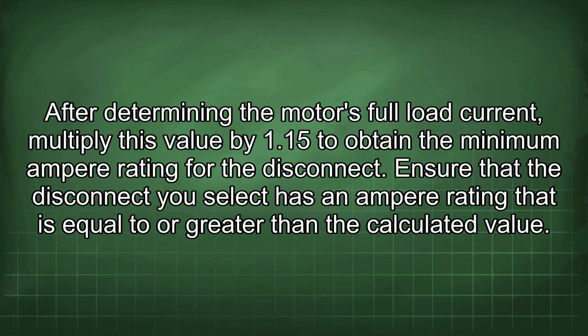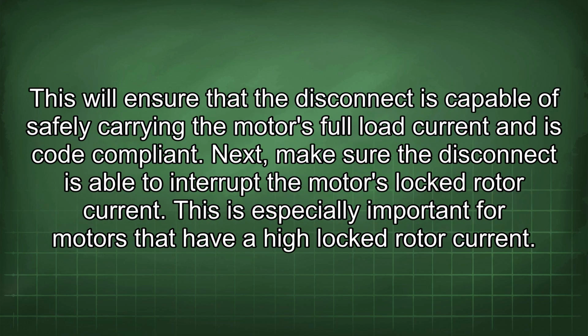After determining the motor's full load current, multiply this value by 1.15 to obtain the minimum ampere rating for the disconnect. Ensure that the disconnect you select has an ampere rating that is equal to or greater than the calculated value. This will ensure that the disconnect is capable of safely carrying the motor's full load current and is code compliant. Next, make sure the disconnect is able to interrupt the motor's locked rotor current.